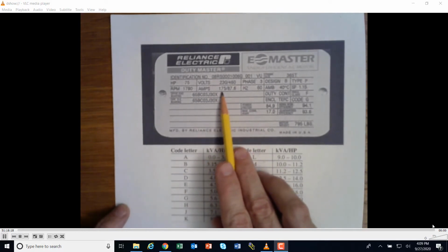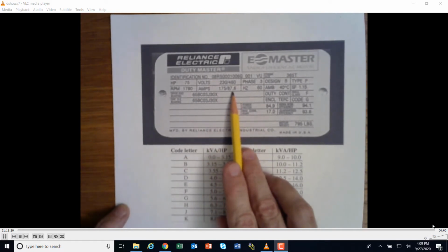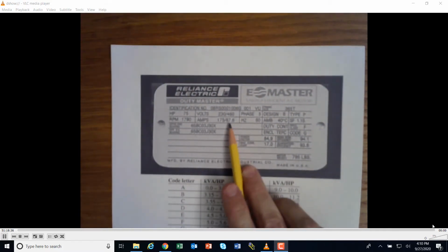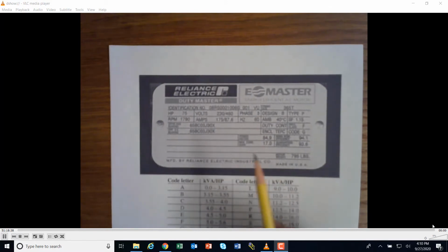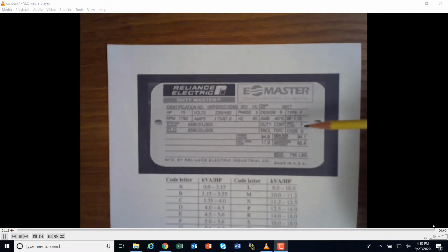Amps is 175 or 87.6. Okay, so amps at the low voltage we'd be running 175 amps, which is a lot, or 87.6 at the 460 volts. So that's a pretty heavy wire that we're going to be running to this. It's 3-phase, 60 hertz. It's going to have a service factor of 1.15.